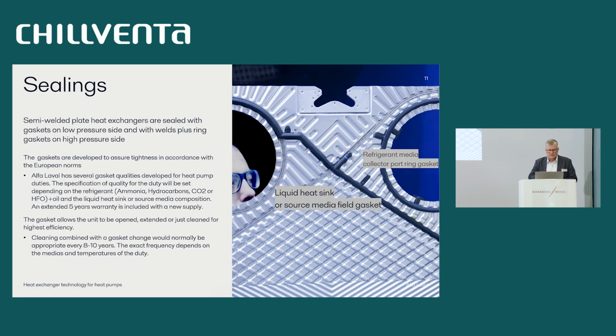The semi-welded heat exchanger is made up of cassettes that are sealed with a gasket on the low pressure side, and on the high pressure side we have welds plus rings. These gaskets and seals can be selected for the different media, depending on the refrigerant, whether it is ammonia, hydrocarbon, CO2 or HFO, plus the oil, and depending on the source media on the other side.